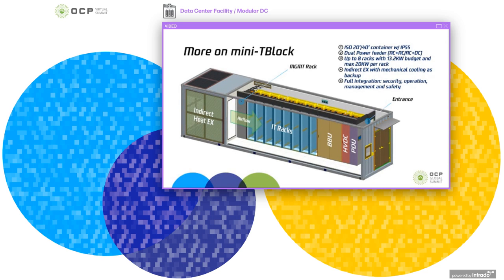It has dual power feed with AC, or AC plus DC enabled, up to 8 racks, and normally we could provide a 13.2 kilowatt per rack power budget, with a maximum per rack power budget of up to 20. Indirect evaporative cooling has been used, and we could also use mechanical cooling as a backup solution. All required systems and components for security, operation, management, and safety have been installed.